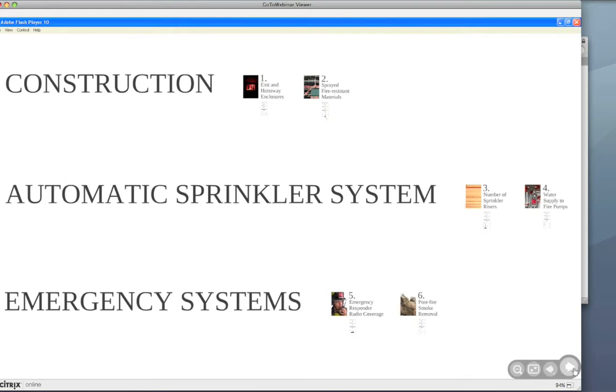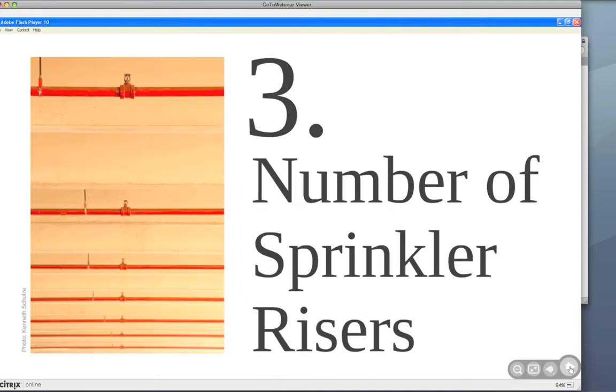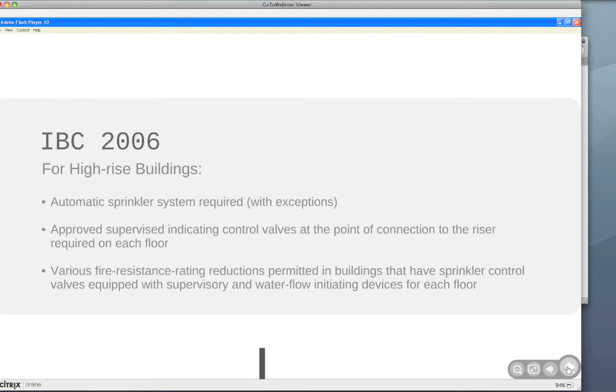Continuing on to the third change, we're jumping on to the automatic sprinkler system changes for high-rise buildings. The first change we're going to look at is in the number of sprinkler risers. Now, in IBC 2006, some of the main sprinkler requirements, specifically for high-rise buildings, were that automatic sprinkler systems were required, with exceptions such as open parking garages and telecommunication towers. Also, approved supervised indicating control valves at the top point of connection to the riser were required on each floor in high-rise buildings, and various fire-resistant rating reductions were permitted in high-rise buildings that had sprinkler control valves equipped with supervisory and water flow initiating devices for each floor.